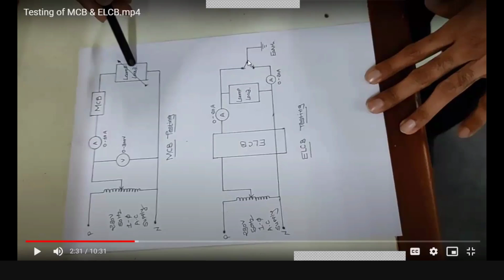From the DP/DT switch we will create the fault. First we will connect this earth wire to the phase, then in the second condition we will connect the earth wire to the neutral and measure the current. When we connect the DP/DT switch to earth, the ELCB will trip, and when we connect the earth wire to the neutral, in that condition also the ELCB will trip, meaning it will disconnect the supply from the load.